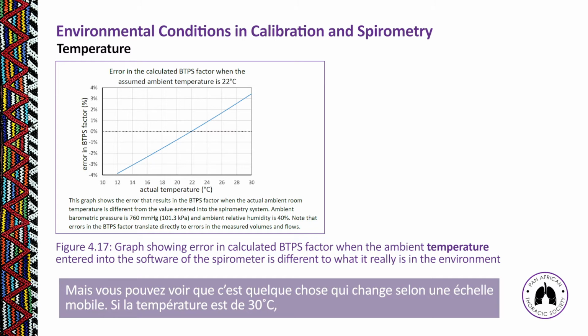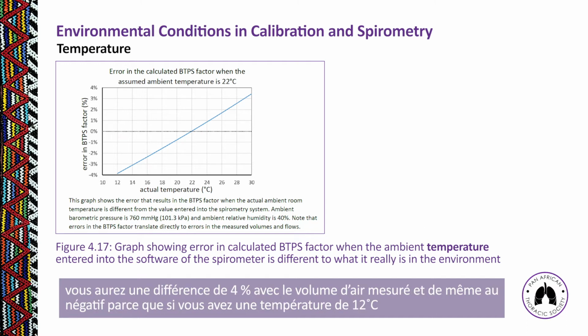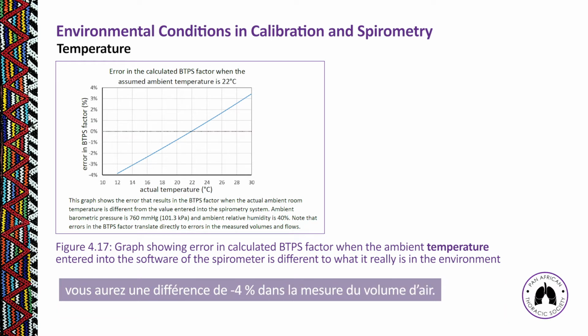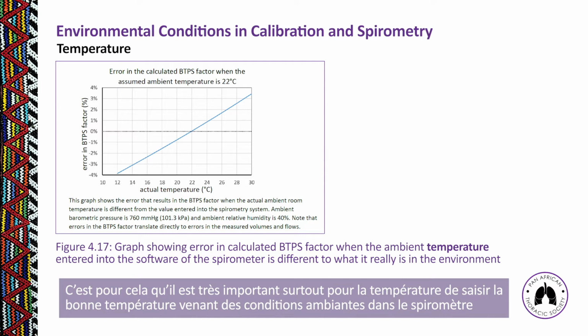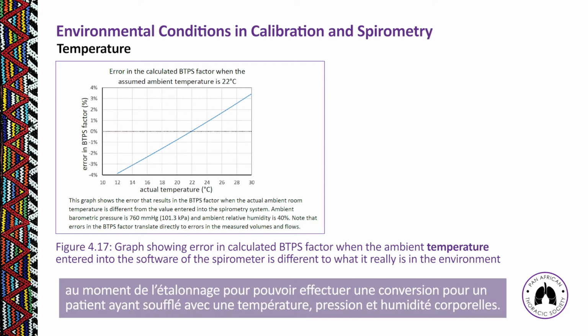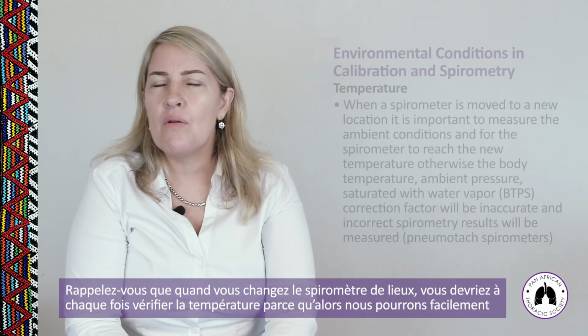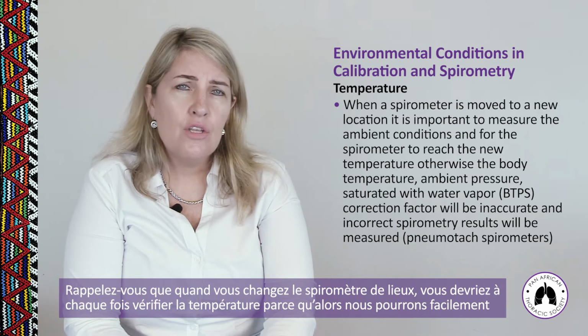If the ambient temperature is 30 degrees Celsius, that will give you 4% difference in the measured volume of air, and the same in the negative. So if it is 12 degrees Celsius, you will see that there will be a minus 4% measurement of volume of air. So it's very important with temperature especially that we enter the correct temperature from the ambient conditions at the time of calibrations so that a conversion can be made to accept a patient who is blowing with body temperature, pressure, and humidity.